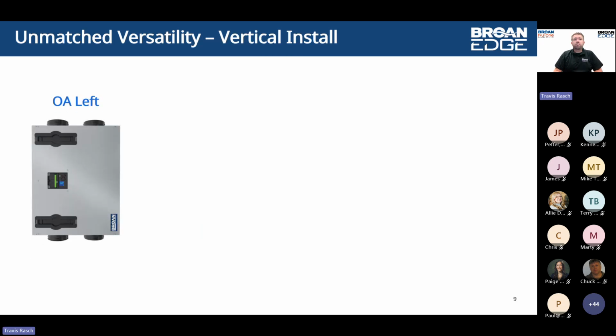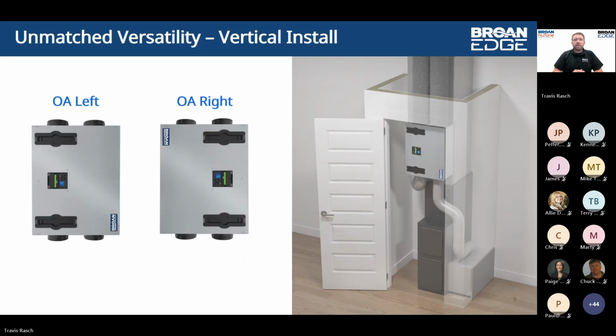A true differentiator for this new Broan Edge platform is the ability for it to get mounted in this vertical orientation, meaning the ducts run vertically. You can see a great example there on where this could be advantageous. On the right side here, if you got a tight mechanical closet, you got a short return there, or even an open air return for that matter.